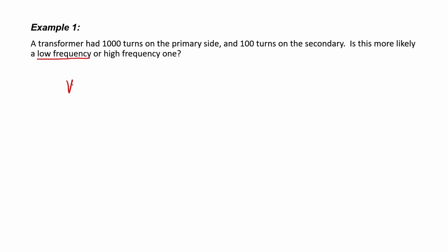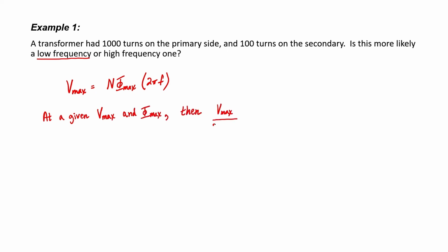To see why, let's recall our expression for the maximum voltage in a transformer. At a given voltage and a given flux, the only two variables in this equation are really N and f, multiplied times one another. So when I see that the number of turns is high, it tells me that the frequency is probably low, because if the number of turns were lower, then the frequency would probably be higher.